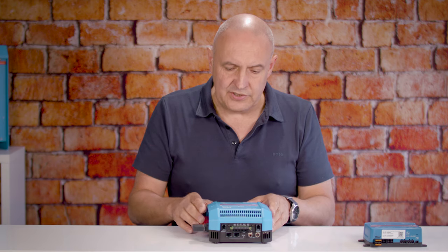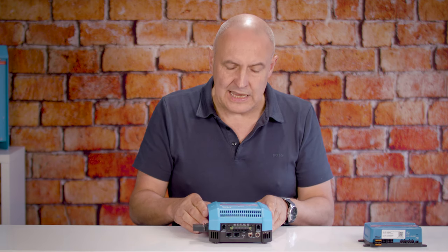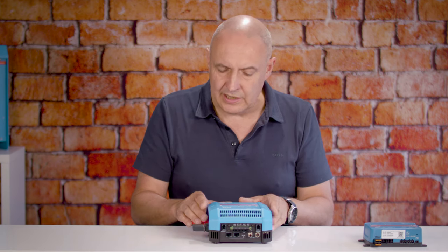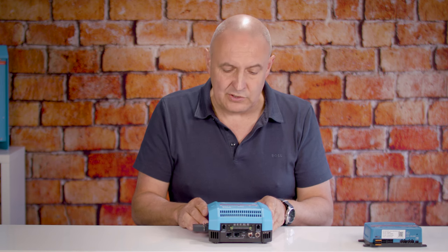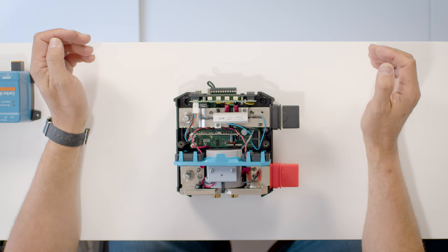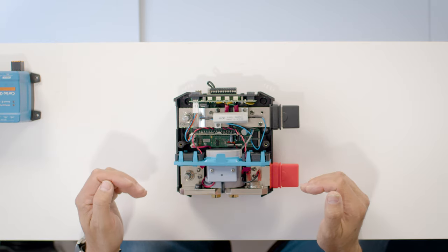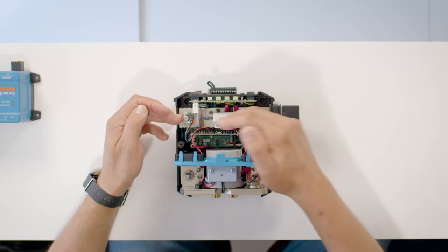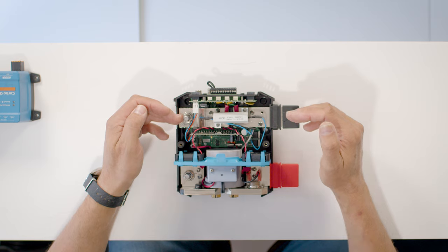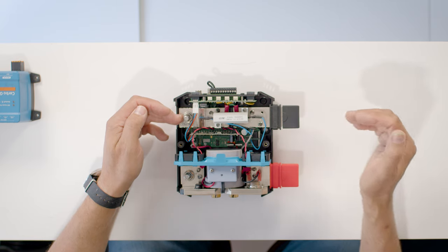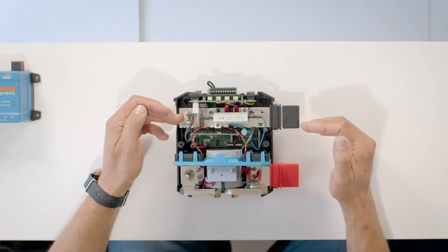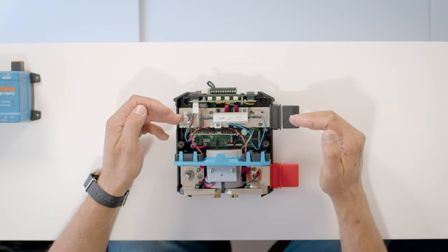So if we have a quick look inside, I'll point to some of the key components, again, just for a matter of interest really, and to give you a bit of the topology of the unit. Broadly speaking, the Lynx BMS consists of a negative busbar with a shunt, and that shunt allows us to record the amount of current flowing in and out of the batteries, and in so doing, record the state of charge or calculate the state of charge of the batteries.